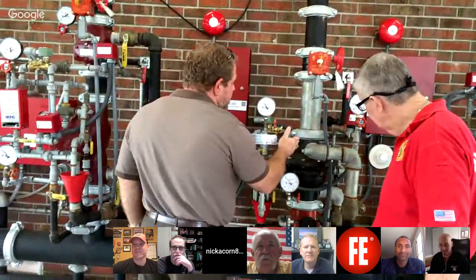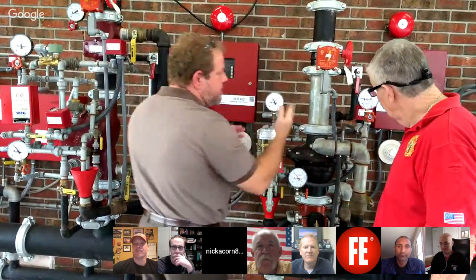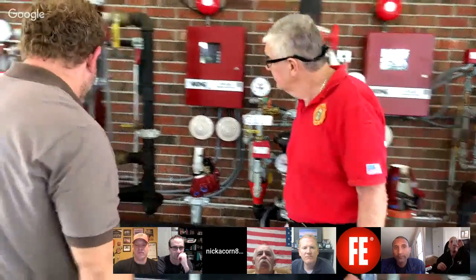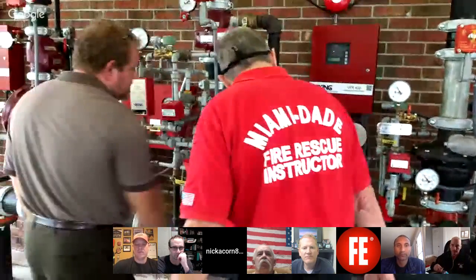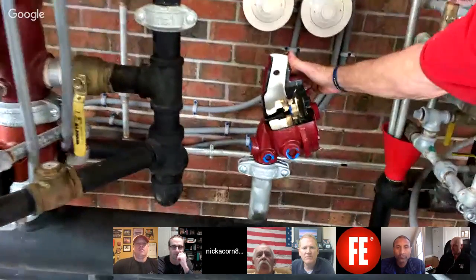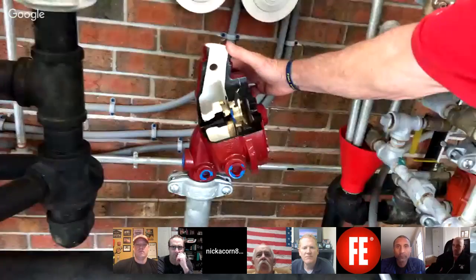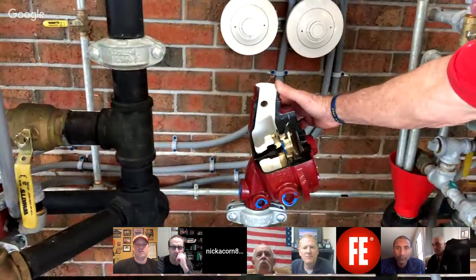We've added the valves above the deluge valve just simply because we want to do full-scale trip tests these days. So this is a newer way of doing it. We're actually tripping the system. But it's not a deluge system, but there's a deluge valve. Correct. Deluge means open nozzles. These are closed head systems, both single and double interlocking. What we've been able to acquire is cutouts, and I think that's critical. If I can follow the water and have someone describe to me the path and flow of water, then I can understand what's inside.